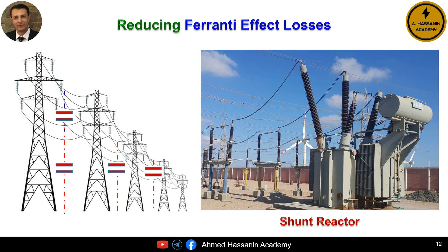Therefore, the only solution or the best method to treat and reduce the problem of voltage rise at the end of the transmission line is to avoid the occurrence of the Ferranti effect by connecting a shunt reactor at the receiving end of the transmission line. The main function of installing a shunt reactor is to absorb or consume the excess reactive power. Reducing the amount of reactive power means lowering the voltage value, and thus we can avoid the voltage rise. By doing so, we prevent the occurrence of the corona phenomenon or the limits of partial discharge on the overhead line insulators, transformers, and other electrical equipment. Consequently, this leads to a significant reduction in electrical losses.